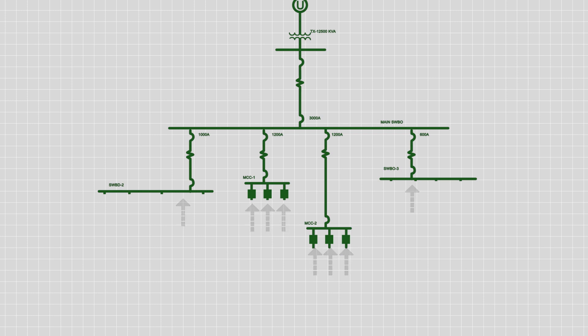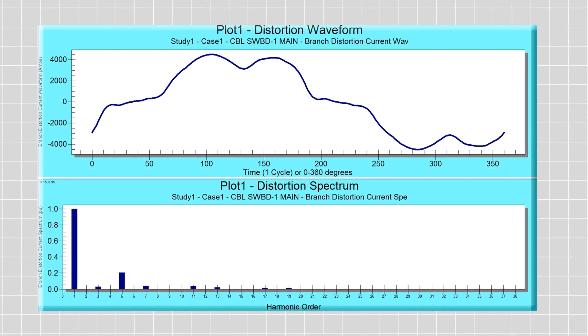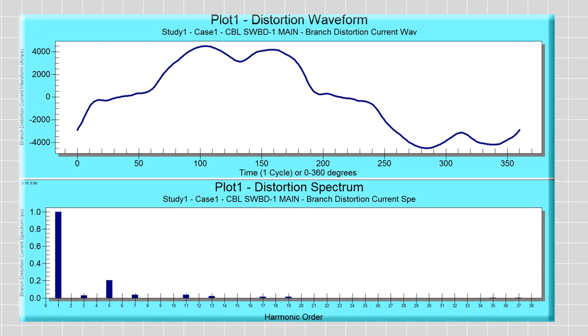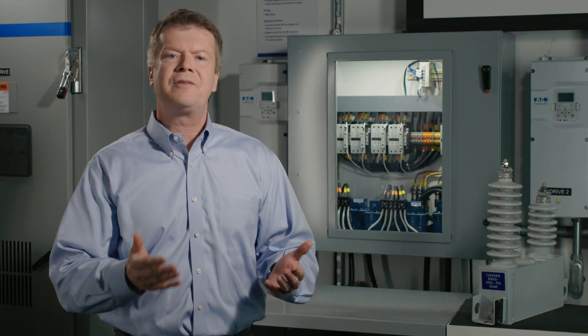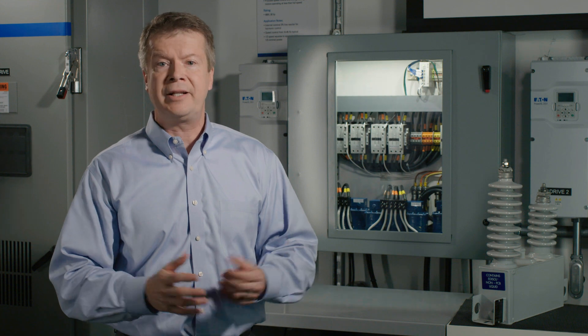This points out that the load flow study is a prerequisite for a harmonic study. This harmonic study will show how harmonic currents flow through multiple parallel and series paths according to the impedance, and the result is a corresponding harmonic voltage drop at various buses in the system. Essentially, it is a load flow starting at the loads and flowing back towards the source, exactly opposite of the traditional analysis. This is done for every harmonic order — third, fifth, 19th, etc. — that exists on the system.